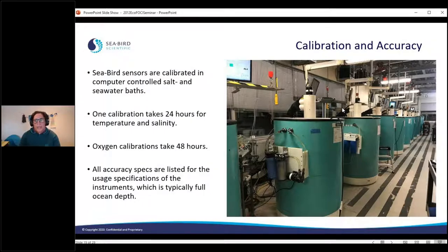The next part is really calibration and accuracy. This is a picture of one of our calibration labs at Sea-Bird. We actually have a whole bunch of them. Each one of these green bins has probably about 6 to 8 sensors in there, and they're in there overnight getting calibrated. A calibration bath is pretty much an extremely stable bath that you put your instrument in and compare it against a reference. Then you try to understand what that calibration is, and figure out the coefficients you need to make to the calibration equation to get 1 degree C or 1 PSU or whatever it needs to be. So all of these are calibrated in computer controlled salt and seawater baths.